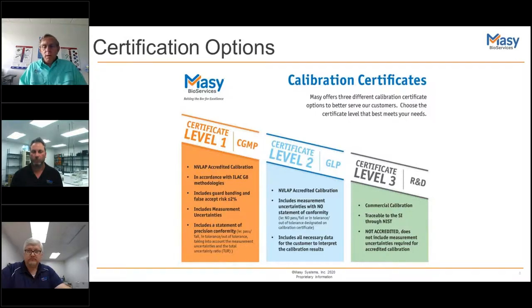So the level three, it's typical commercial calibration. It is traceable through SI and NIST, absolutely, using the same standards we would use for an accredited cal, same standards. Absolutely, yes. And it's not accredited.